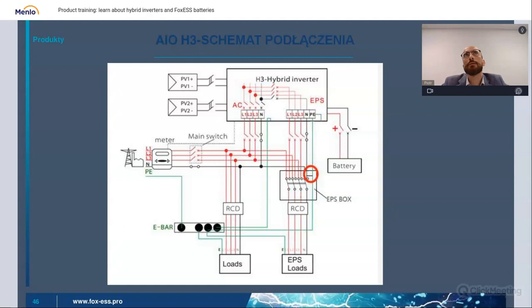Everything is connected nicely. There you have your EPS box. This is a bridge between the N line and the ground line. And this is added because you may have a TN-C or TN-S type of grid. You may use it to bridge those two lines together, depending on the type of grid that you operate. You may use it on every TN-S and TN-C or so.